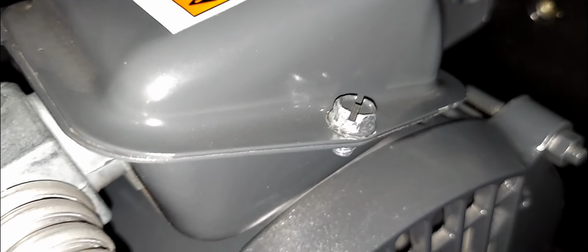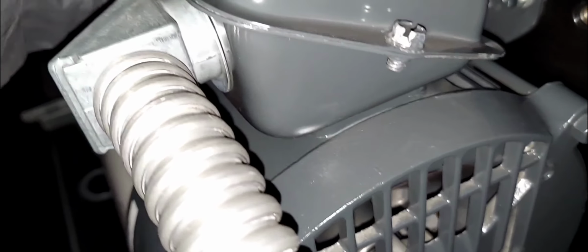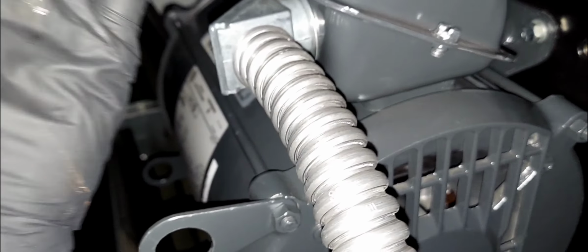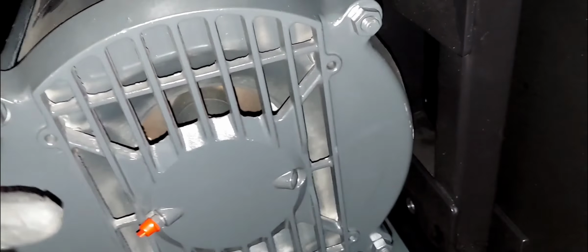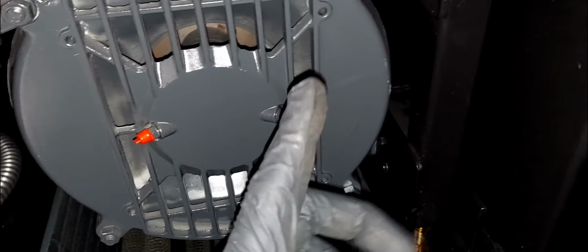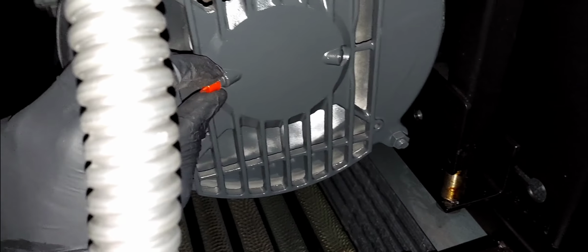Alright, so I'm going to go ahead and open up the pecker head right here. And these look like 3/8. And we're going to see what's inside. There should be a safety or a sensor in there that's preventing this fan from running. Must be tripped. Okay. I remember some of these units, they actually have a button on the motor which you can press to reset it when it's tripped. But I don't see any button on this one. This right here is for greasing. So I'm going to open up the pecker head and see what I see.